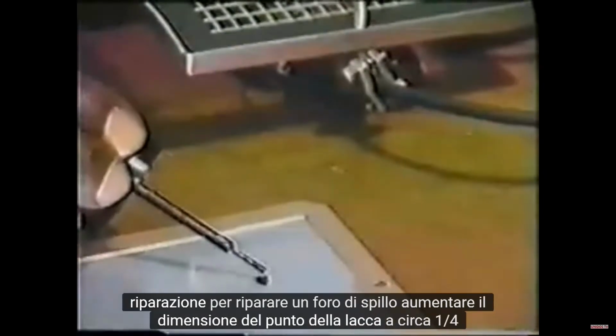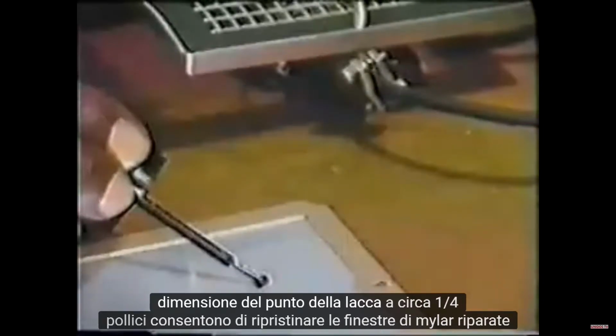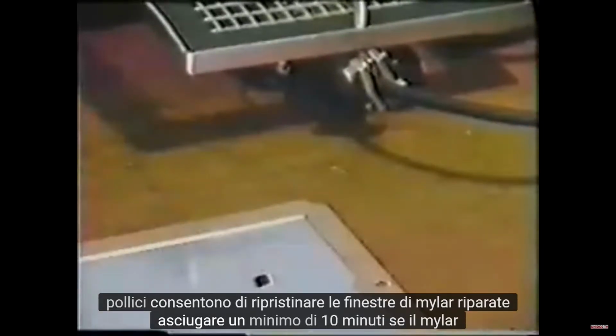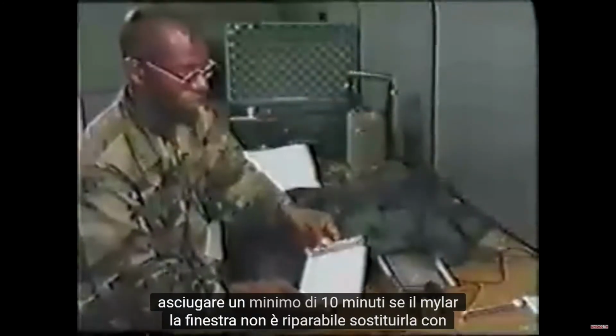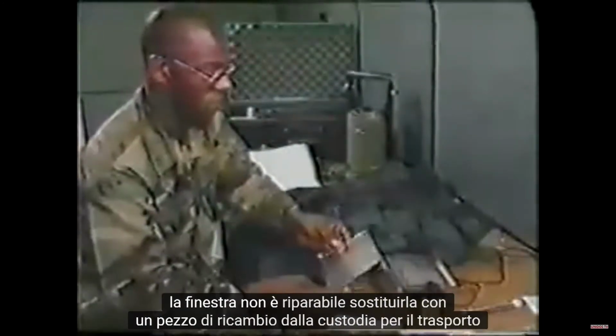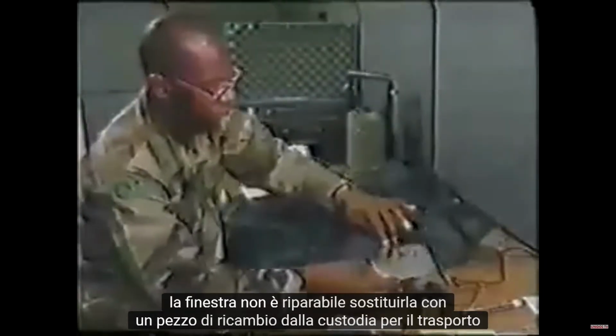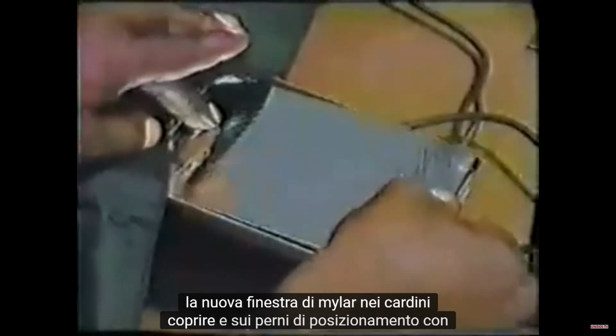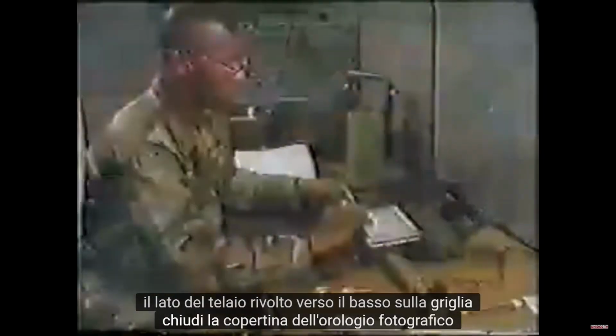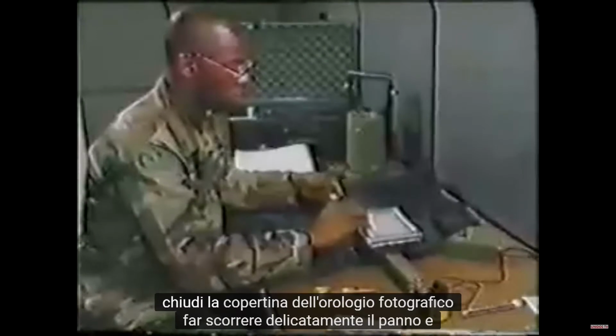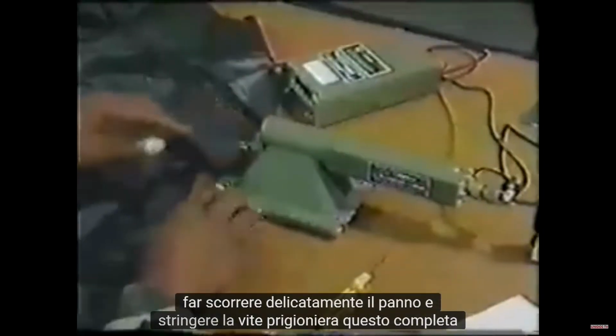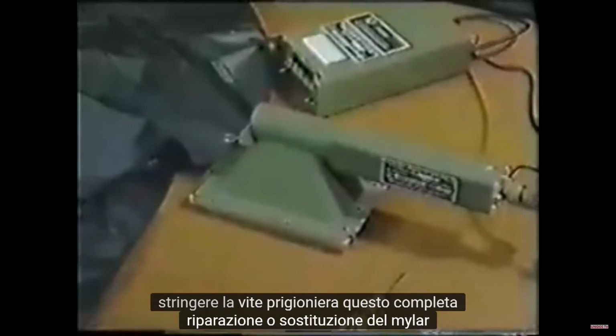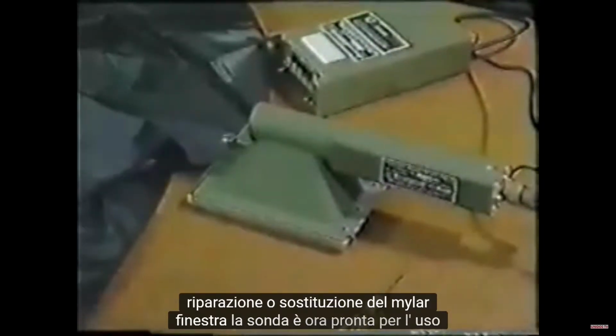To repair a pinhole, increase the size of the lacquer dot to about 1/4 inch. Allow the repaired Mylar windows to dry a minimum of 10 minutes. If the Mylar window is not repairable, replace it with a spare from the carrying case. Install the new Mylar window into the hinged cover and onto the locating pins with the frame side facing down on the grill. Close the cover on the photo cloth. Carefully slide the cloth out and tighten the captive screw. This completes repair or replacement of the Mylar window. The probe is now ready for use.